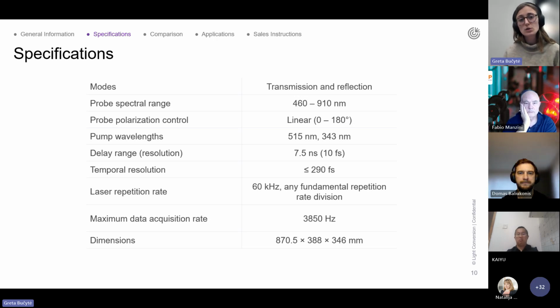Delay range now in Harpia Lite will be 7.5 nanoseconds. Temporal resolution is around 290 femtoseconds. If we have a laser with slightly better specs, the temporal resolution will be better. Laser repetition rate maximum will be 60 kilohertz, but we can pulse pick it and have 1 kilohertz or whatsoever. Maximum data acquisition rate will be similar to Harpia TA, 3.8 kilohertz. Dimensions are here.